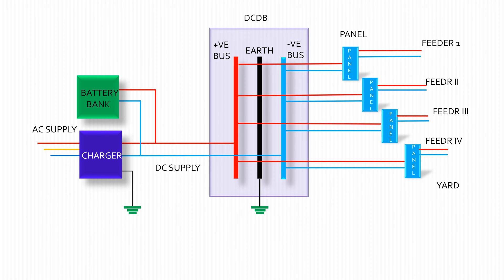The DC supply system of a substation is a very important subject. For its reliability, it plays an important role for uninterrupted power supply — as circuit breaker closing, tripping operation of different relays, indication and annunciation etc. depend on this DC supply. So it is called the heart of the substation.